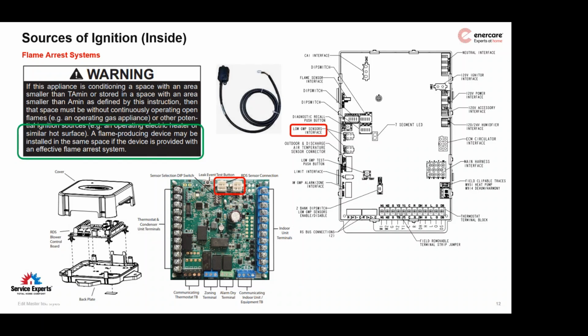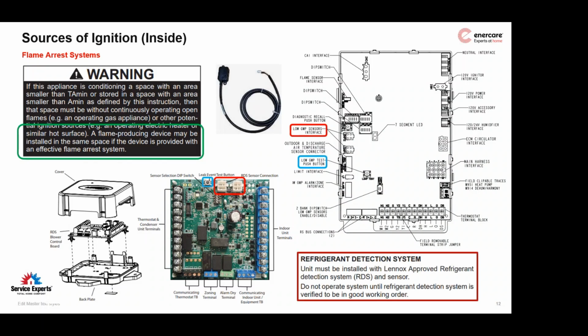There we go. There's a look at one of those sensors, and its wiring harness, test buttons, sensor locations. This is one key note I want to make sure that everybody takes away with them. When these are being installed, the small test button that's highlighted in blue will need to be used specifically on this one. You push it once, and we'll get into it a little deeper, to make sure that the units actually shut down the heating or cooling and go into fan only so that there's dissipation, and the control board will tell you it's in dissipation mode. But we'll get into the specifics of that further on.